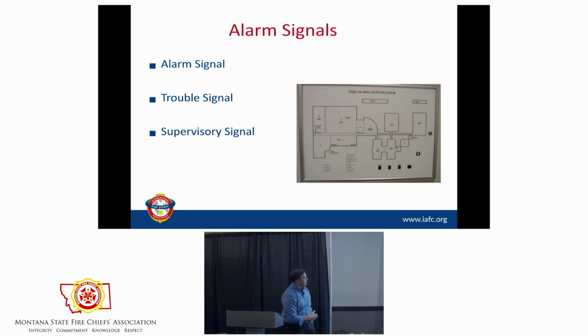So there are 3 signals: alarm, trouble, and supervisory. Why is this important? Alarm is when the fire department comes. Trouble and supervisory are other things, right? Supervisory is intended to tell the occupants to go do something. Trouble would be as if you cut a wire, okay? A gate valve closed is a supervisory signal. You respond to an activation of a water flow device, you pull up, you go to the panel. You see water flow system 1, water flow system 2, and then as you scroll through the panel, you see closed control valve or supervisory main control valve. Does that change your order of operations? It should, because we need to find out why the sprinkler system's closed.